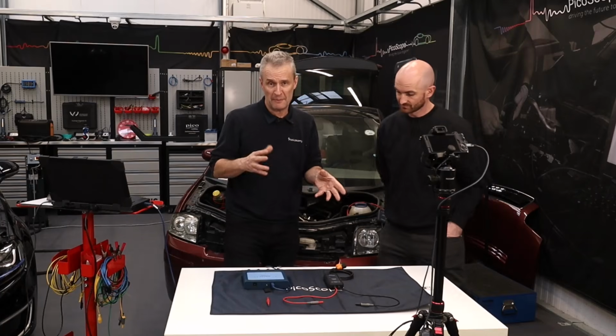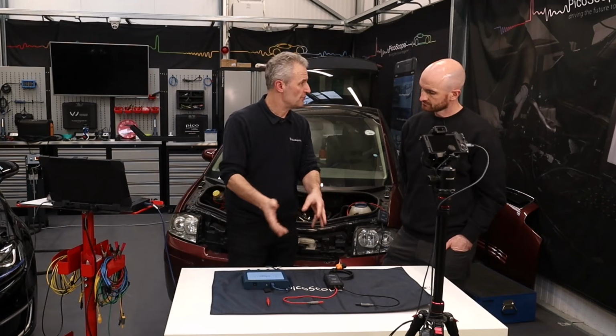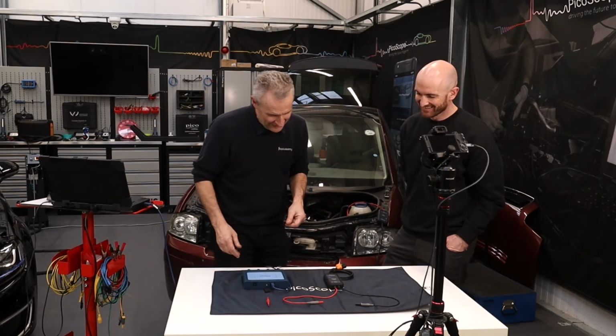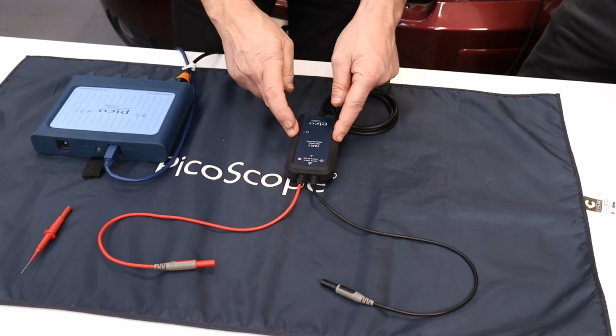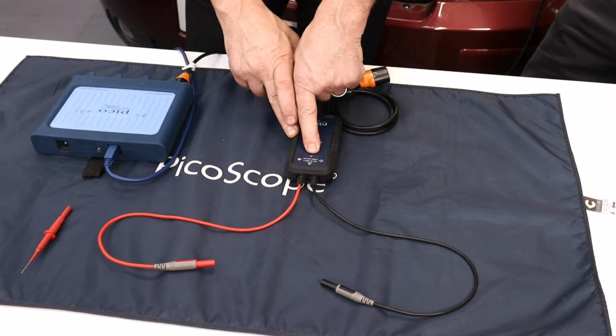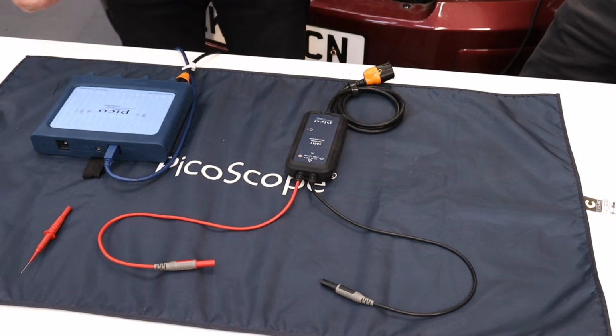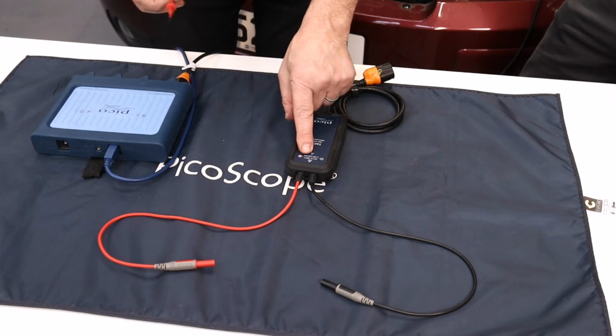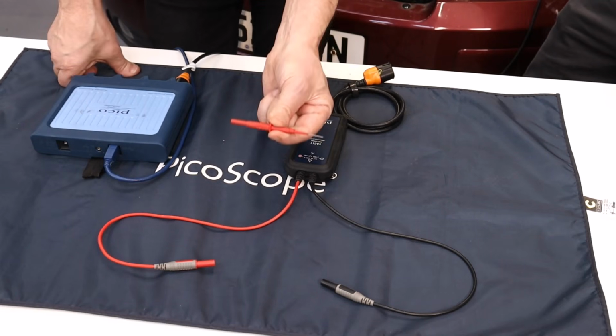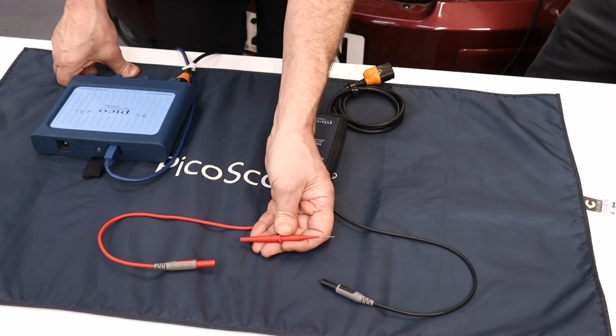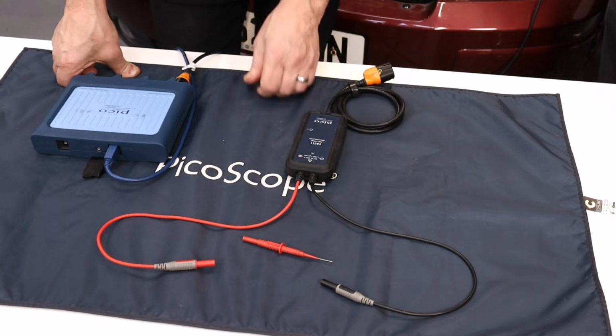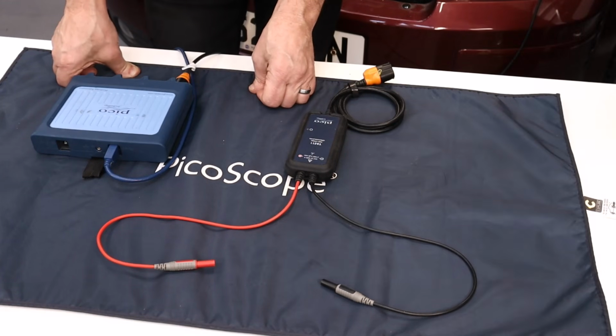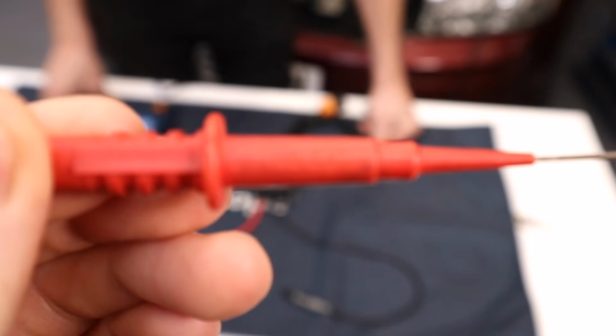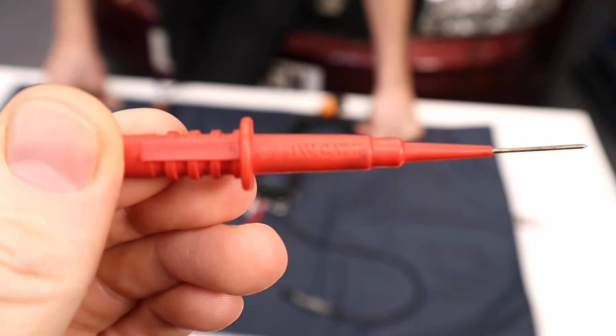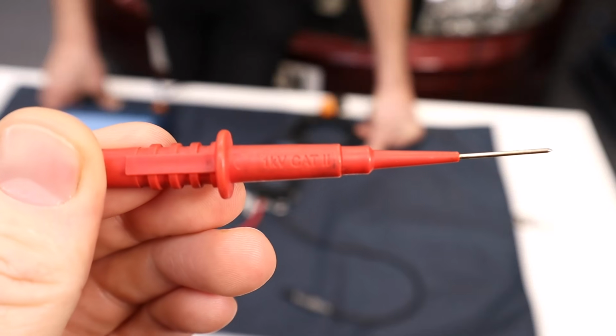There are those who'd be more upset about possible damage to a probe or scope than yourself, but hey. So you've got that cat rating in here. This is Cat 3, 1000 volt. Now on that note, whilst this is Cat 3, our backpinning probes, for example, if you were measuring the CP circuit on an electric vehicle, are Cat 2 rated, because they have that exposed tip, which means the highest cat rating they could achieve is Cat 2.